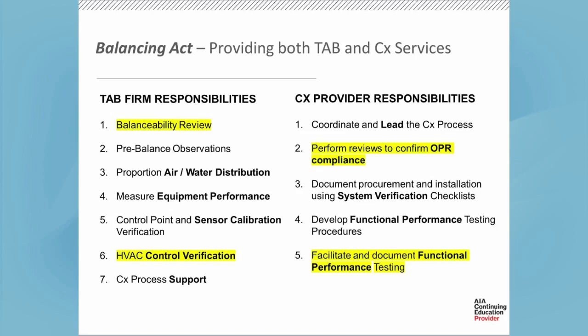With respect to some of these responsibilities, the TAB firm - and we're referencing AABC national standards for total system balancing here - would be responsible for performing a balanceability review, pre-balance observations, proportioning air and water distribution, and measuring equipment performance, which includes thermal performance and many other things. That's a simplified statement. Also control point and sensor calibration verification, overall control verification meaning sequence verification, and supporting the commissioning process.